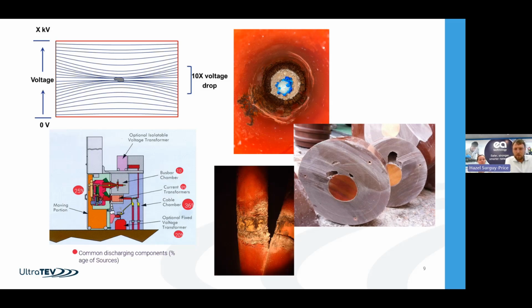The top picture with that lovely blue colour at the base is actually a spout off a live network. You can see on the left-hand side and toward the back some carbonisation. That carbonisation is tracking - surface tracking, surface breakdown of the insulation - where these little sparks, this PD activity, have started to eat away and shorten that conductive path, leading towards a flashover. Just a reminder, that's come off a live piece of equipment.